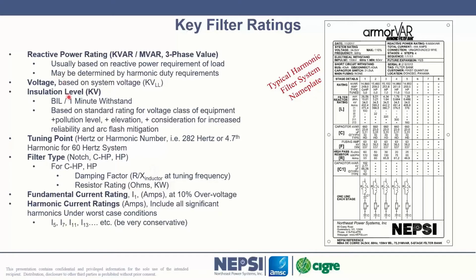Next key rating is voltage. Obviously, if we have a 33 kV system, the kvar output is based at 33 kV. It's your line-to-line voltage rating. Then the insulation level, the impulse rating, and the 1 minute withstand. That's based typically upon the base voltage of the system, plus elevation concerns, plus pollution concerns. Those types of concerns can also raise the insulation level, the impulse rating, the BIL we call it, and the 1 minute withstand rating, which is a 60 hertz or 50 hertz application of voltage at the terminals of the filter bank.